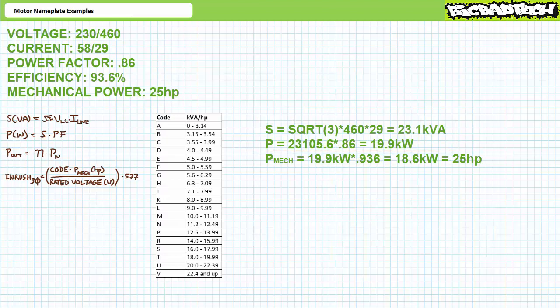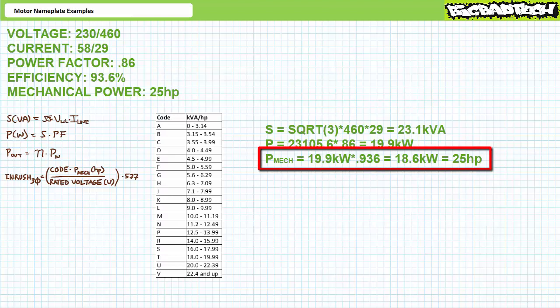Note that when experiencing the rated condition, the motor operates at 93.6% efficiency. An algebraic rearrangement of the efficiency formula solved for unknown output demonstrates output equals input times efficiency. Substituting our given values demonstrates this motor must be producing 18,599 watts, or more appropriately 18.6 kilowatts. A unit conversion demonstrates 18.6 kilowatts is roughly equivalent to 25 horsepower — extremely close to the nameplate mechanical power of this motor.